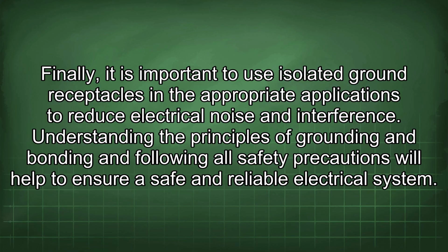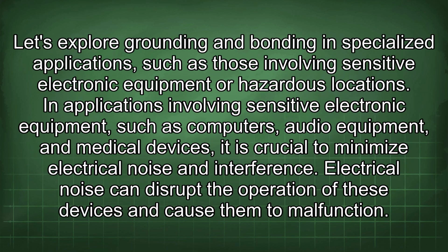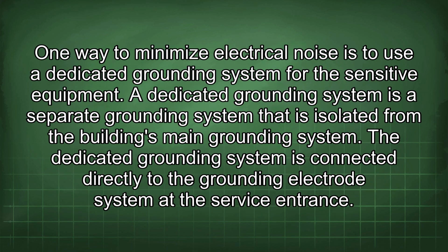electrical system. Let's explore grounding and bonding in specialized applications, such as those involving sensitive electronic equipment or hazardous locations. In applications involving sensitive electronic equipment, such as computers, audio equipment, and medical devices, it is crucial to minimize electrical noise and interference. Electrical noise can disrupt the operation of these devices and cause them to malfunction. One way to minimize electrical noise is to use a dedicated grounding system for the sensitive equipment. A dedicated grounding system is a separate grounding system that is isolated from the building's main grounding system.